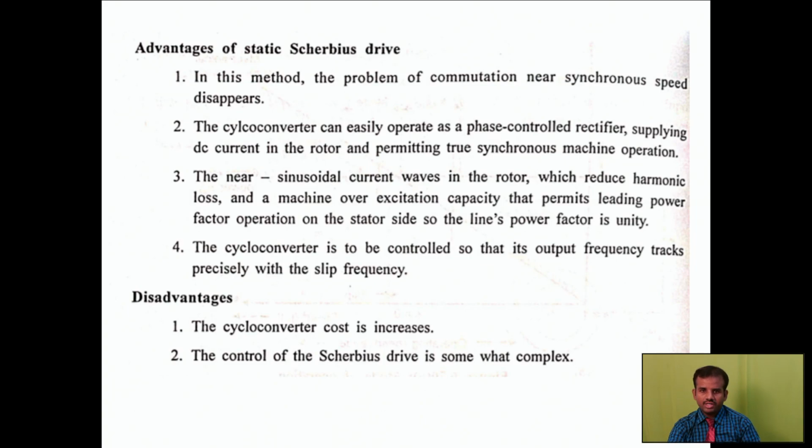So the advantages of static Scherbius based drive. In this method the problem of commutation near the synchronous speed disappears. The second point is the cycloconverter can easily operate as a phase controlled rectifier, supplying DC current in the rotor and permitting true synchronous machine operation. Then next, near sinusoidal current waves in the rotor reduce harmonic loss and give machine over excitation capacity, which permits leading power factor operation on the stator side.